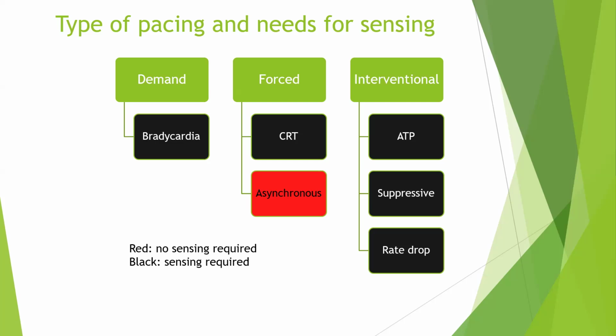Force pacing, on the other hand, is when we want the pacemaker to pace all the time or most of the time. And this is basically the biventricular pacemaker for heart failure. Although the patient has intrinsic rhythm, the intrinsic rhythm is not favorable because it results in dyssynchrony, and as a result, the left ventricular cardiac output drops. And we want to improve that by making the pacing basically come from the biventricular pacemaker. So this is a kind of force pacing, but to be able to work, it needs intrinsic sensing. The pacemaker must be able to sense the P wave, and then depolarize the ventricle faster than what is expected to happen if it lets the P wave go through the AV node.